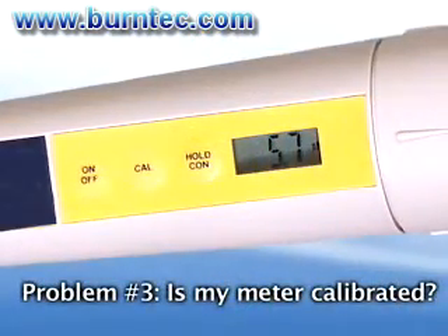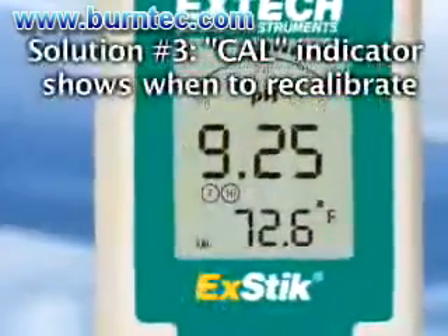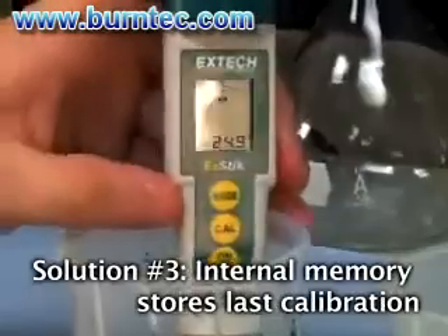Problem number three: How do I know if my meter needs to be calibrated? The ExStik's CAL indicator will appear when it is time to recalibrate the meter. The internal memory will store your last calibration and will display on screen to eliminate any guesswork.